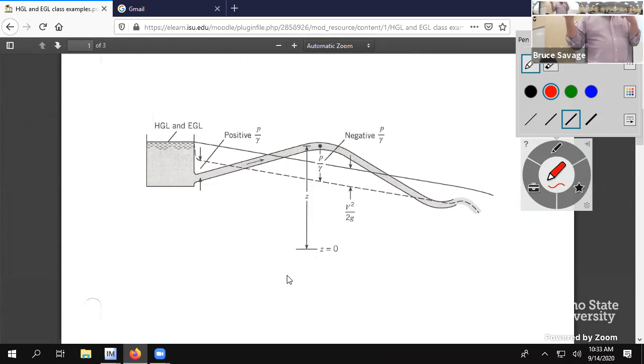But if you apply a little bit of vacuum, does that straw collapse? Oh yeah, like that. Pipelines are the same way. They're extremely good at handling pressure going out. Anytime you get a negative pressure, they just collapse, especially if they have a soil load on the outside that's trying to push them in as well. So they're just going to fold right up, okay? So finding low pressures, negative pressure specifically, is what we want to do.